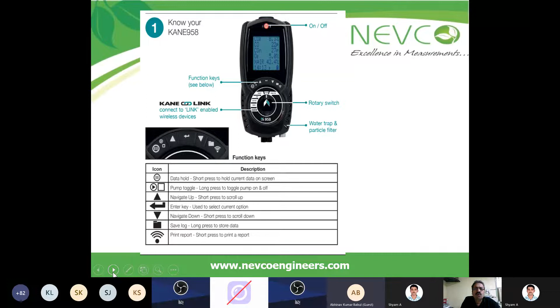These are small units. You can see here there is a sample probe. We have a built-in pump here. And this is another model, 958, which is currently in the market, having a rotary switch, a water trap and particle filter. This is something new they have made. Then there is the 988, which measures not only SO2, CO, CO2, but also NO, NO2 and hydrocarbon. You can always measure these, with a hydrogen compensated CO sensor in the 988 model.